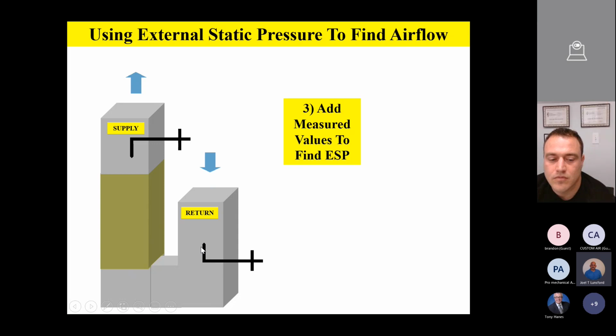So we want to see if this air handler is just sitting like on a box, we could actually poke a hole in the cabinet of the air handler and make sure that pressure probe is pointed down into the airstream, and we'll be reading how much suck that fan is pulling against that pressure probe. Does that make sense? So it's perfectly fine to poke a hole right here in the air handler, like on the side or whatever, and read it that way. That's perfectly fine. Good question. Any other good questions or comments?